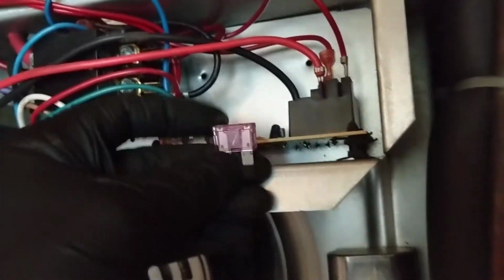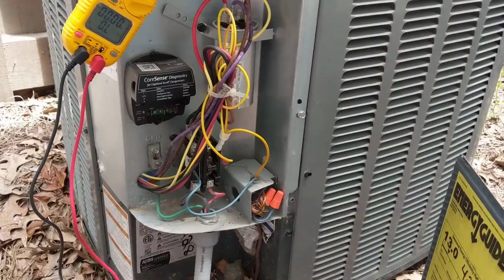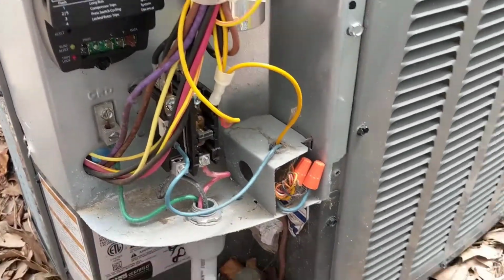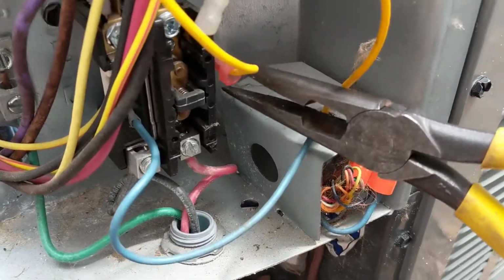I think what we'll do is go outside and ohm out the contactor, see what it's reading, and go from there. Alright, so we'll unhook, pull the power, and we will unhook the short probe tool. And I got a new 3 amp fuse to go back. Alright, so I'm just going to throw this cover back on, and then we'll go out and check out the contactor. Alright, we're at the outdoor unit here now, so we will check the contactor.